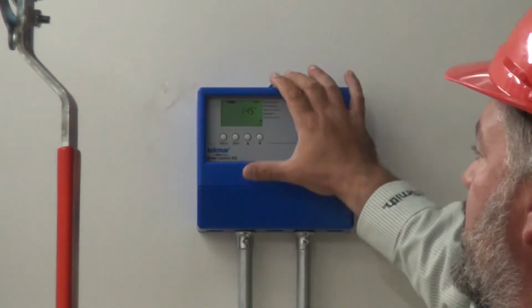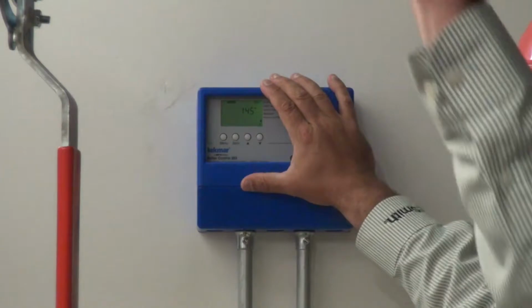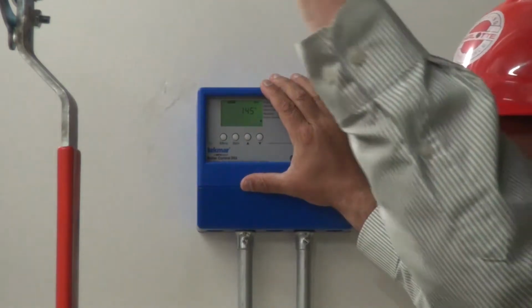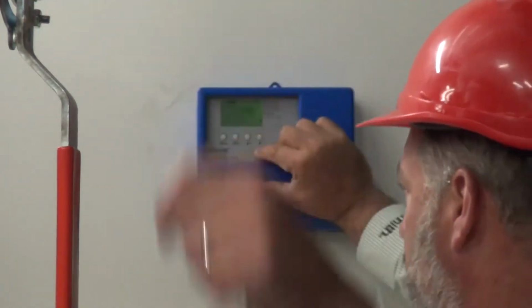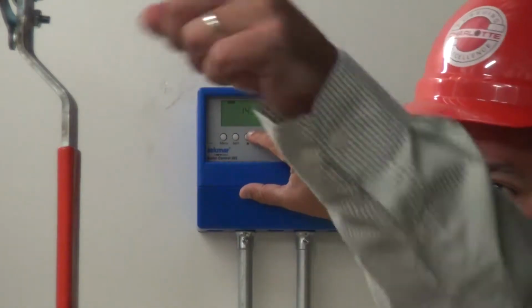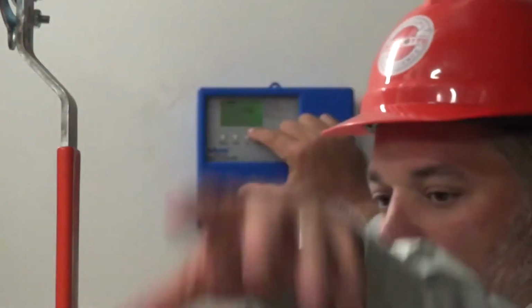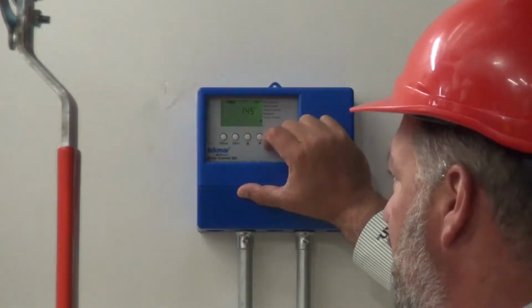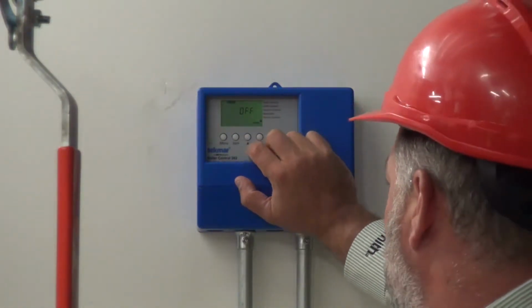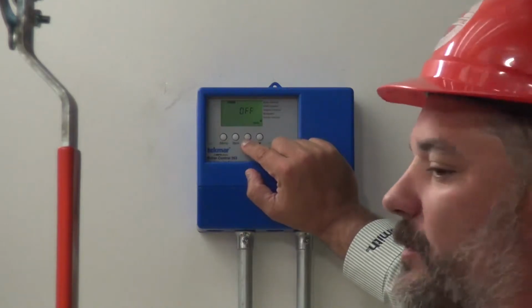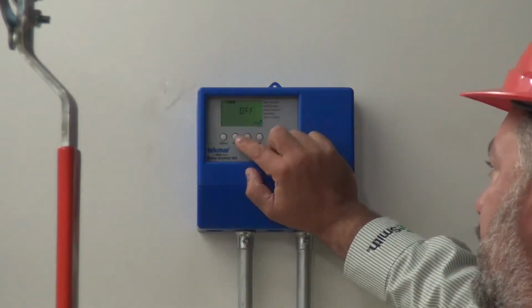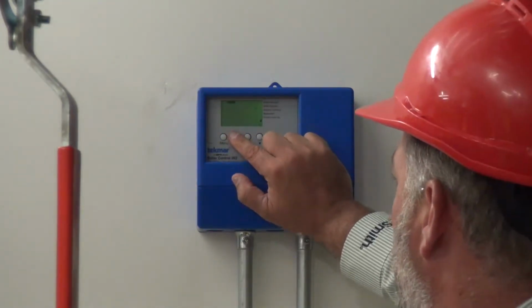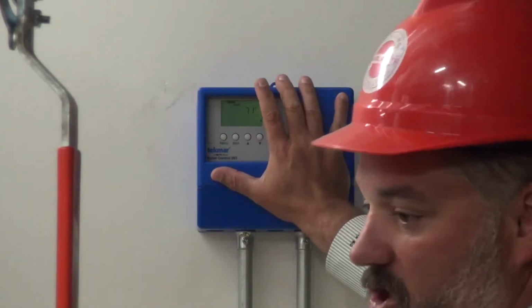And then we can change the temperature of what we want on that unit. So if we wanted a higher temperature on the tank, we can adjust that up, and that's going to control when these boilers kick on. It's going to read that sensor off of there and then turn on these boilers to actually achieve that. And then we've got warm weather shutdown. Again, that's more on a hydronic side, and it's set to off. So those are all really the basics of what you can adjust on here.